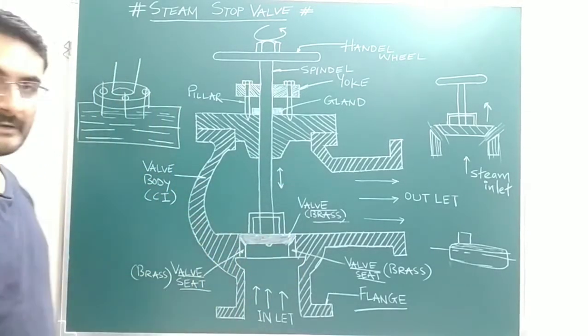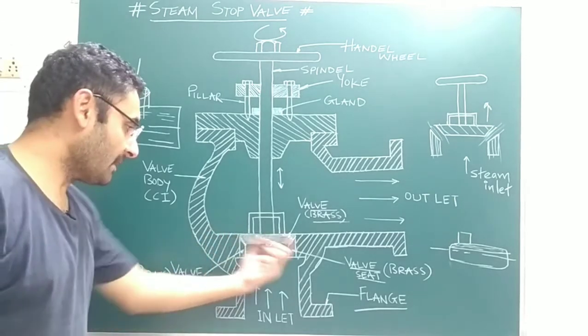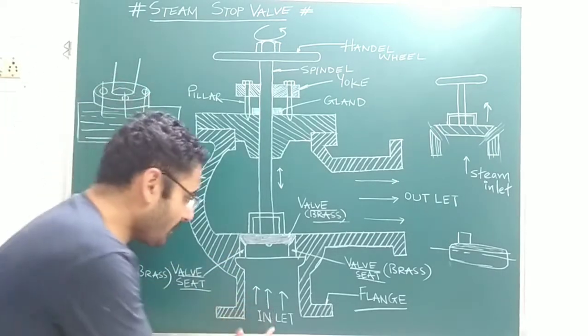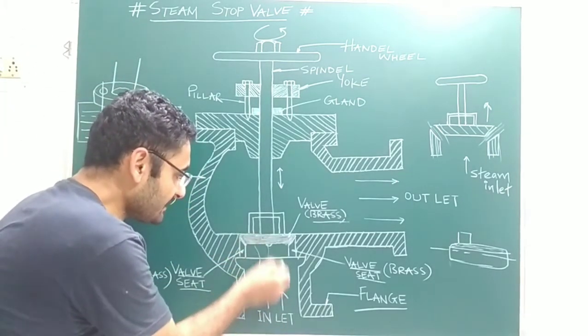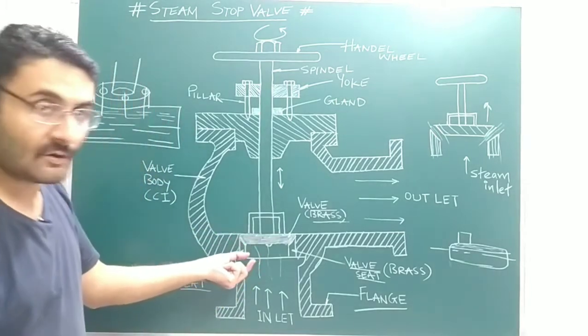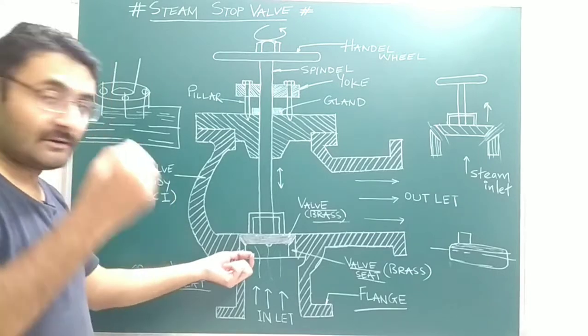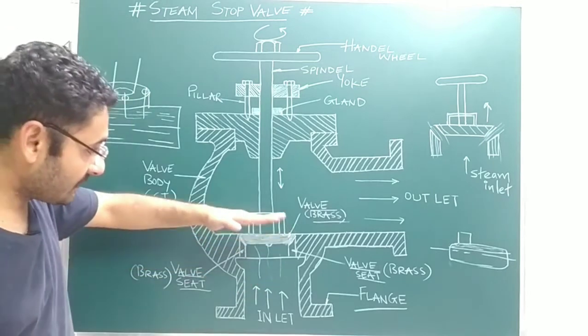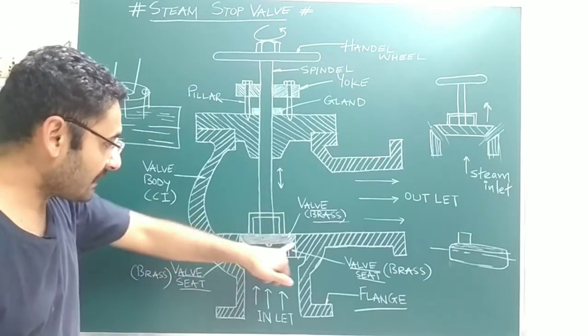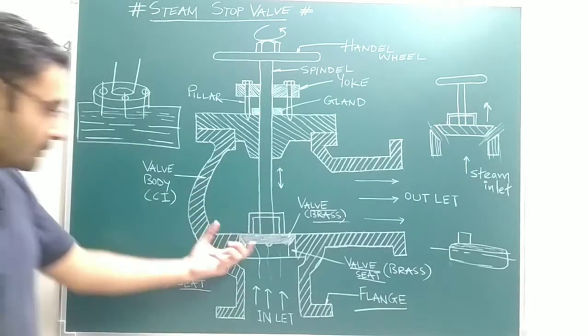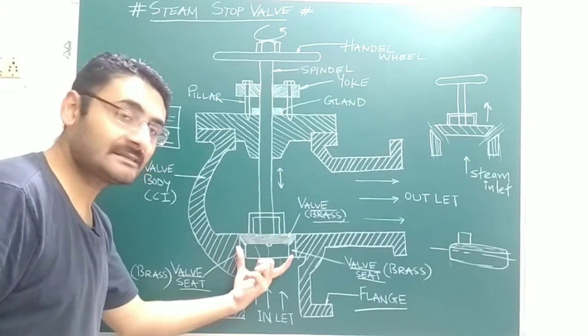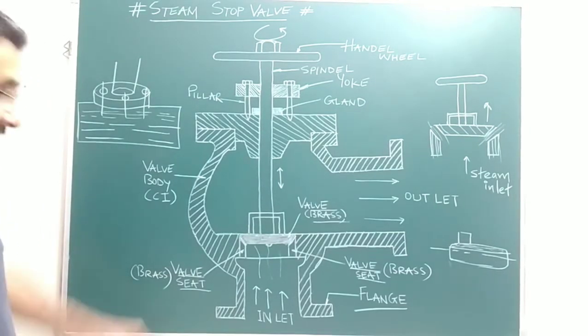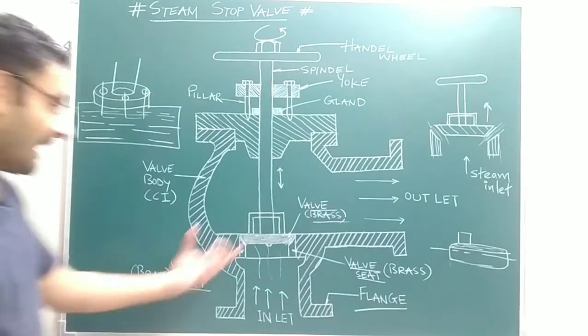A question may arise: why are the valve and valve seat made with brass material? The answer is that steam entering from the inlet contains water particles in the form of vapor. That water may cause corrosion on the valve and valve seat. To avoid corrosion, they are made with brass, because brass is an anti-corrosive material, which gives the valve a longer service life.